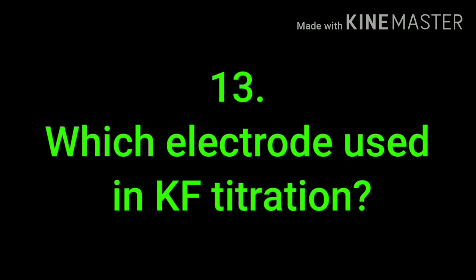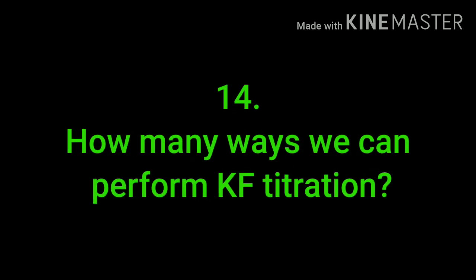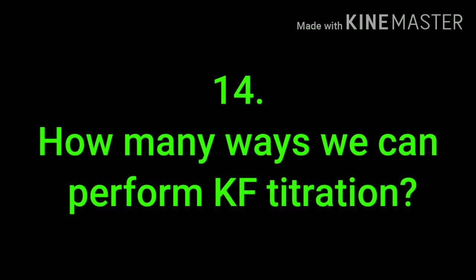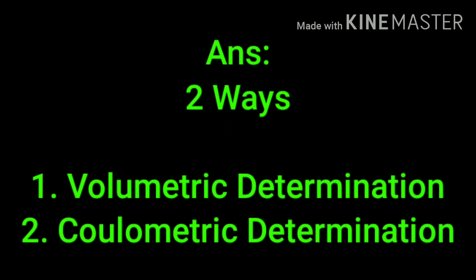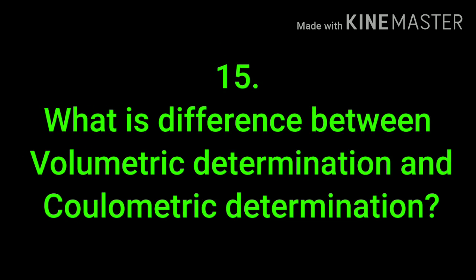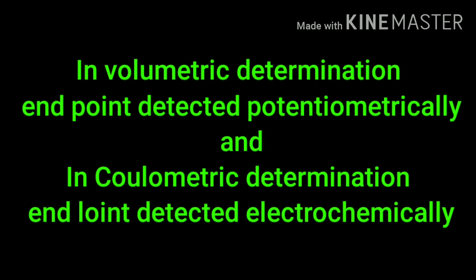Which electrode is used in KF titration? The answer is the platinum electrode. How many ways can we perform KF auto titration? There are two ways: volumetric determination and coulometric KF titration. What is the difference between the two? In volumetric determination, the end point is detected potentiometrically, and in coulometric KF titration, the end point is detected electrochemically.